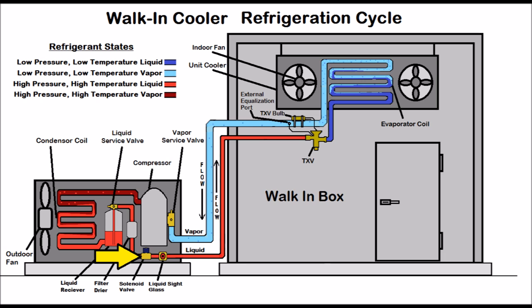On the system you're working on, it may or may not have a solenoid valve. If it doesn't have a solenoid valve and doesn't have a pressure control, then that system is just turned on and off by a mechanical or electronic thermostat. In this case, we're showing a liquid solenoid valve used as a pump-down feature on a system with a low pressure control. The sub-cooled liquid refrigerant heads through the liquid solenoid valve and then through the liquid sight glass.